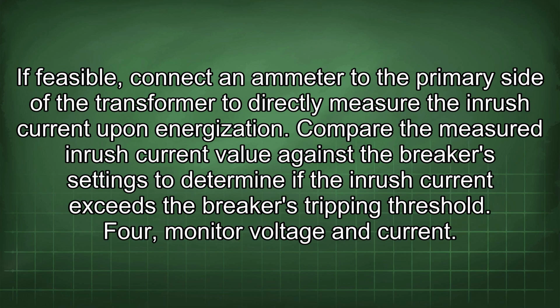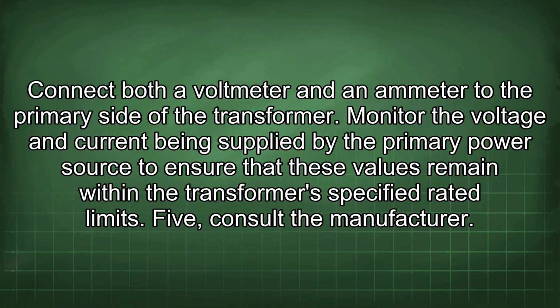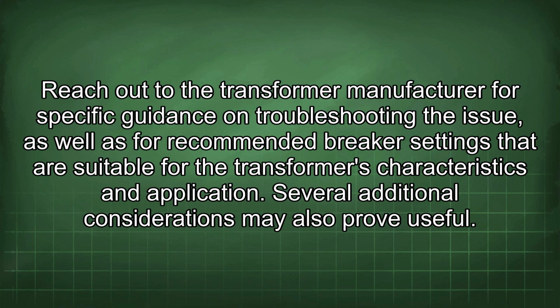4. Monitor voltage and current. Connect both a voltmeter and an ammeter to the primary side of the transformer. Monitor the voltage and current being supplied by the primary power source to ensure that these values remain within the transformer's specified rated limit. 5. Consult the manufacturer. Reach out to the transformer manufacturer for specific guidance on troubleshooting the issue, as well as for recommended breaker settings that are suitable for the transformer's characteristics and application.